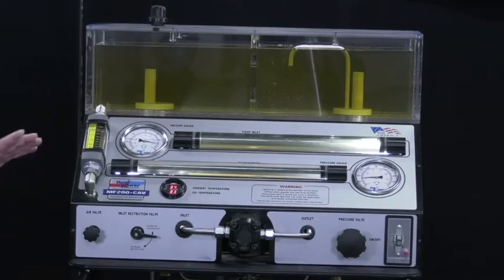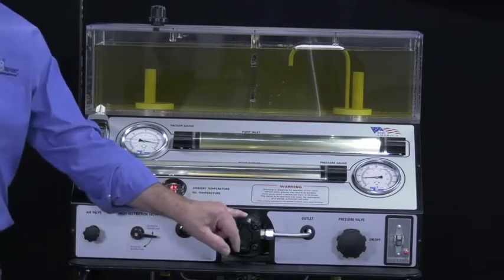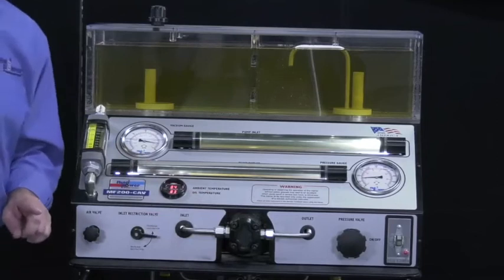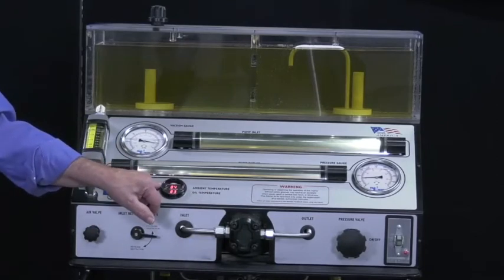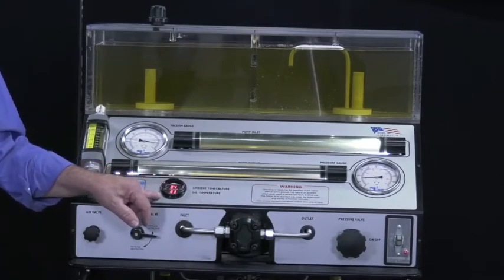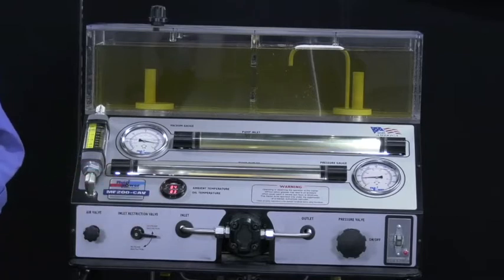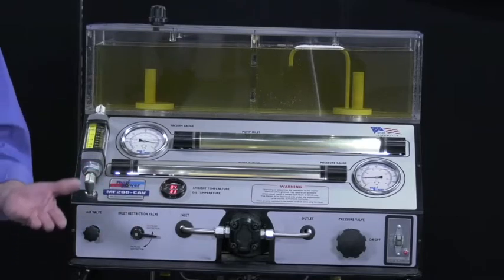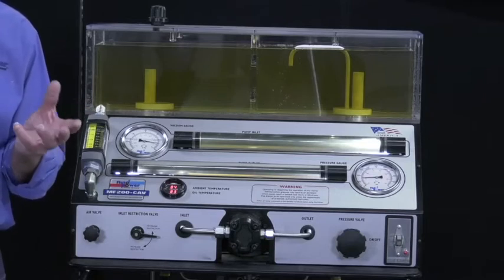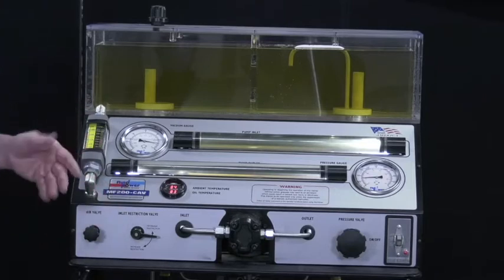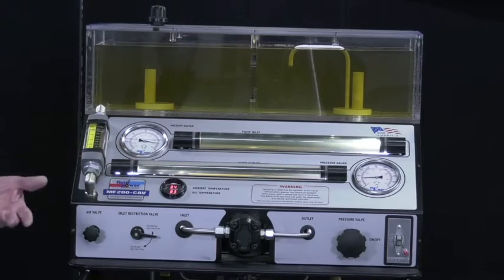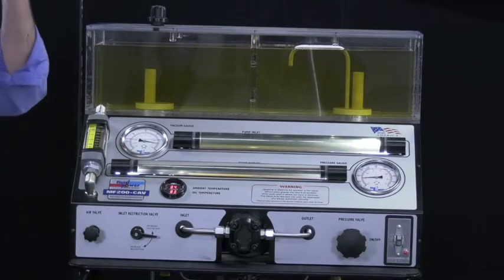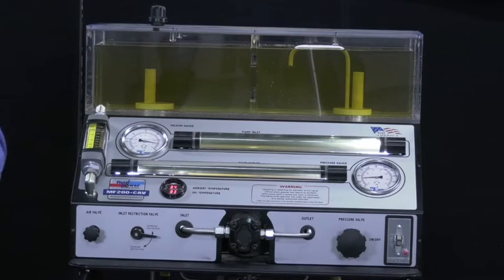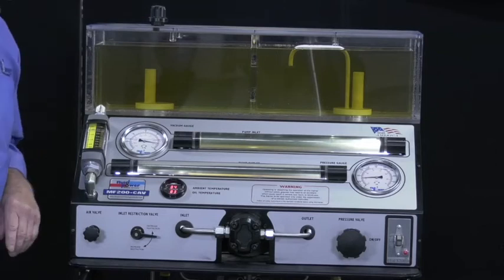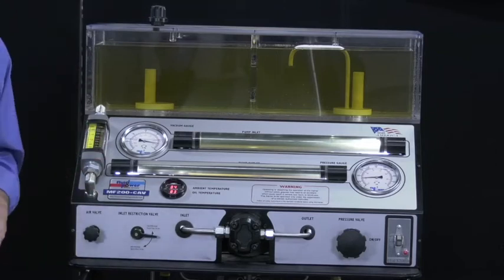All right. So now, my inlet restriction right now on this gear pump is 4 inches of mercury. My ambient temperature is 84 degrees Fahrenheit. My oil temperature is 83. So it's only going to get better. If I wait long enough to go to 135 degrees Fahrenheit, this is only going to get better. This is going to probably go down to 2.5. The lower, the better, but it has to be from a point of reference, which I'll explain in just a moment. All right. Everything's in perfect working condition here.